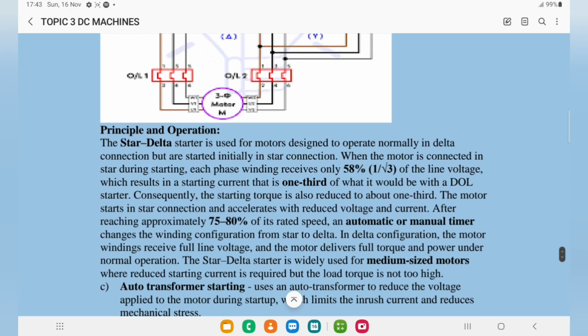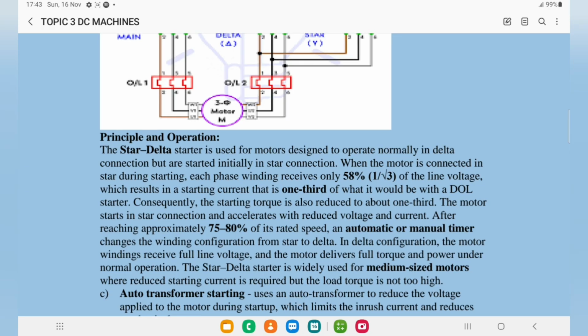When you're talking about the principle of operation, this method is used for motors that operate normally in delta connection but are usually started in a star configuration. When the motor is connected in star, each phase receives only 58%, that is, one over root three of the line voltage. This results in a starting current that is one third of what it would be for a direct online start, when the motor is powered directly. Consequently, the starting torque is also reduced to about one third. So the motor starts in star connection and accelerates with reduced voltage and current to approximately 75 to 80% of its rated or synchronous speed.